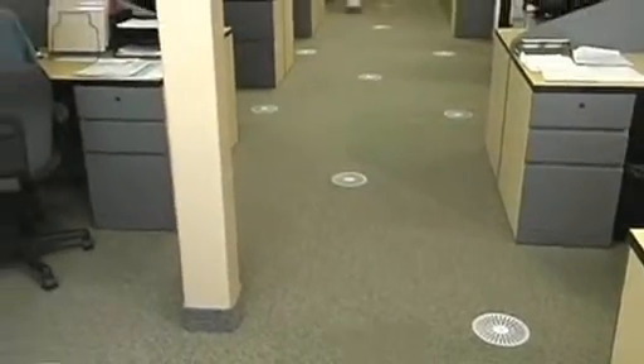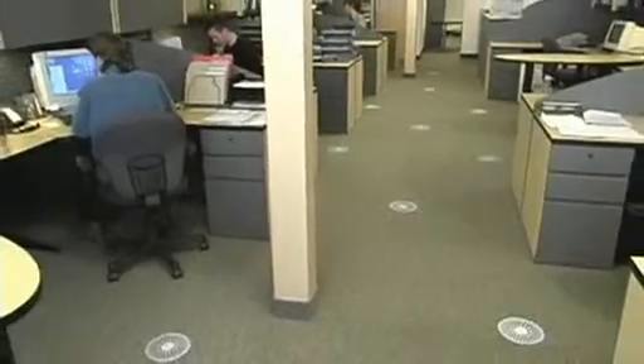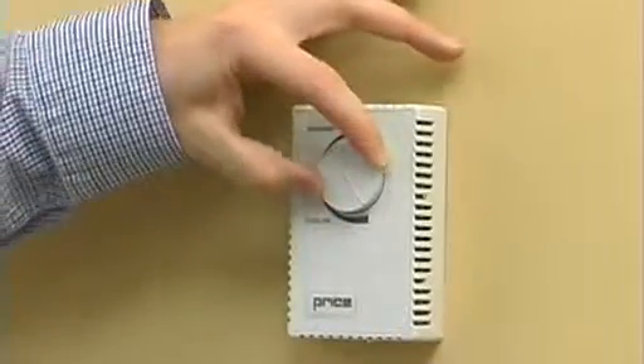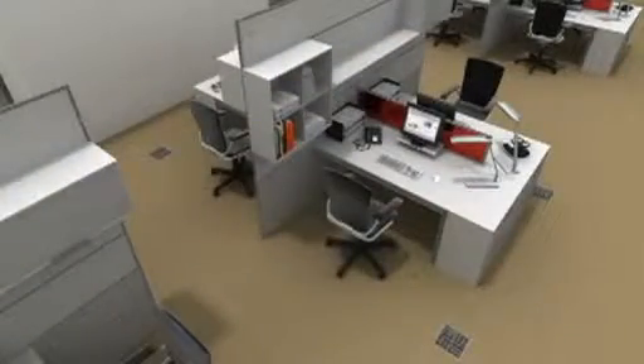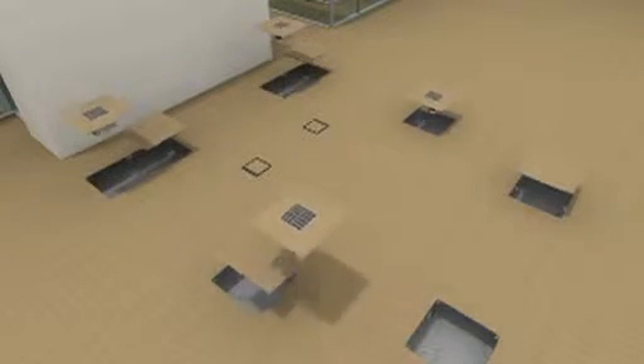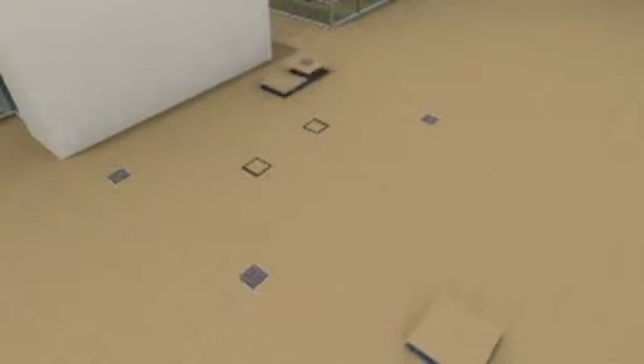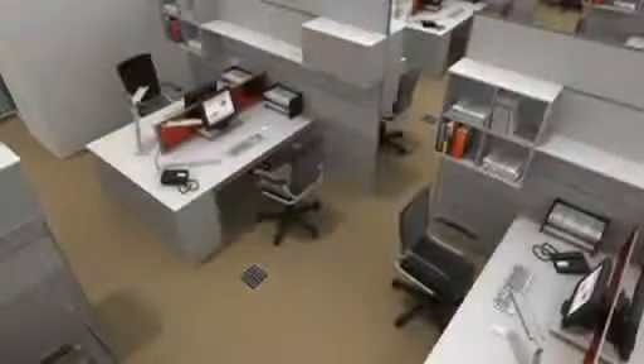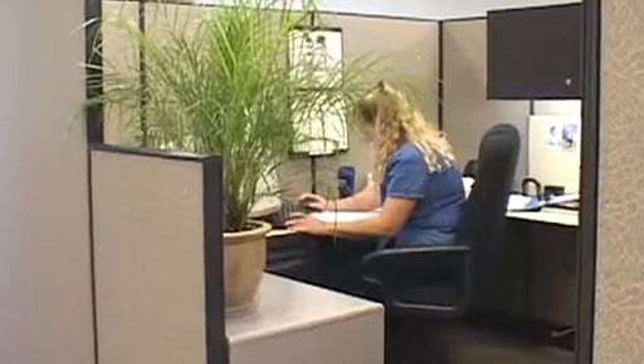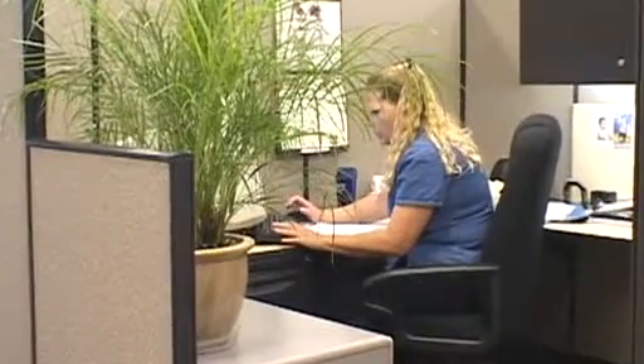No matter why a building is being built, tenant comfort and operability are always considerations. Underfloor air distribution has proven to be an exceptional solution. Underfloor air distribution maintains even temperatures throughout the entire space and uses simple to install thermostats that allow for tenant control in offices or other enclosed spaces. If by chance a diffuser is situated under a desk or some other undesirable position, it's simple to pull up a diffuser tile and exchange it with a full tile from a location more convenient for the diffuser. This is a major benefit in commercial buildings when tenant reconfiguration is required.